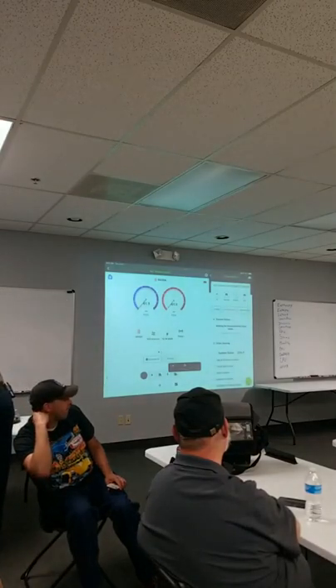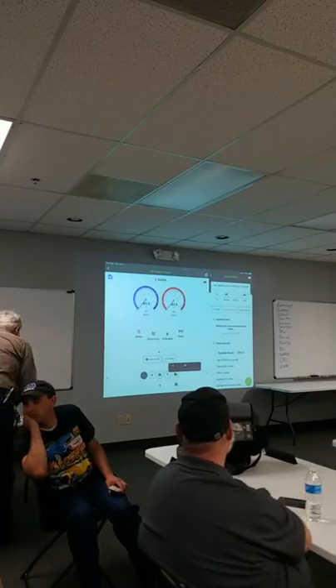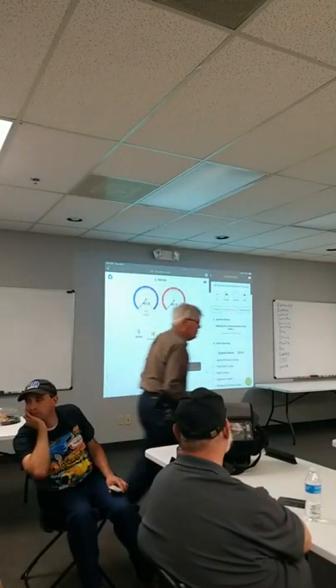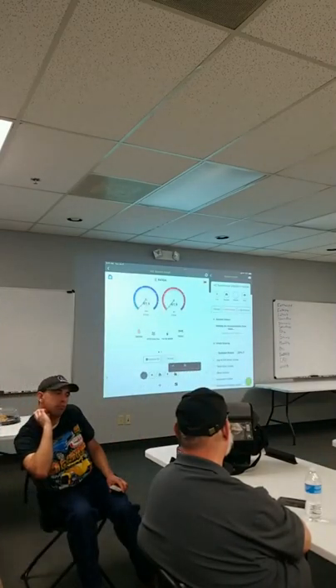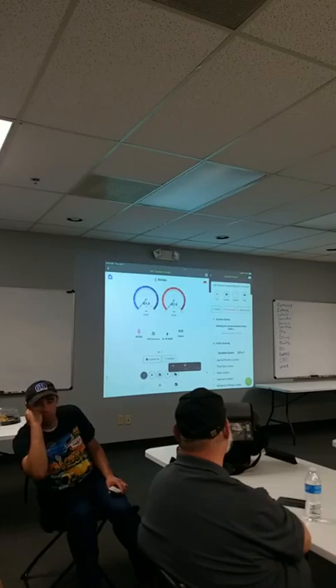You can have a negative latent, but normally that means one of two things happened. The compressor shut off and you're re-evaporating the water off the evaporator coil. Could also be that you have a non-intertwined coil, so you have a split coil with upper and lower, and the water as it's going down from the top is hitting the dry section of the coil and re-evaporating into the airstream. I've seen that happen before. On a multi-circuit coil, if it's intertwined but not quite getting wet enough, as the water drains down it can evaporate and re-entrain into the air. Or you have a condensate drain with an improper trap, and you're trapping water in the evaporator pan, and it's re-evaporating into the airstream. We'll talk more about that.